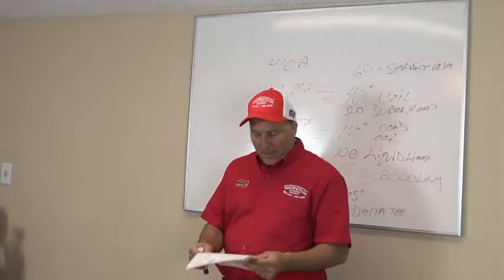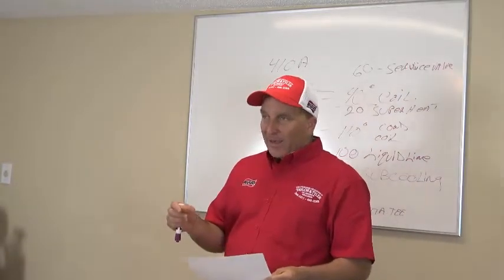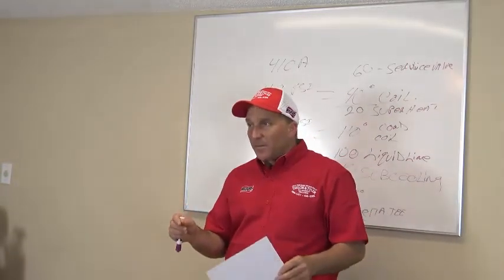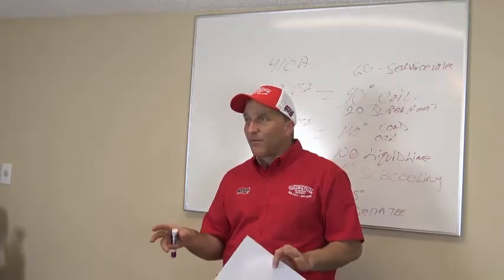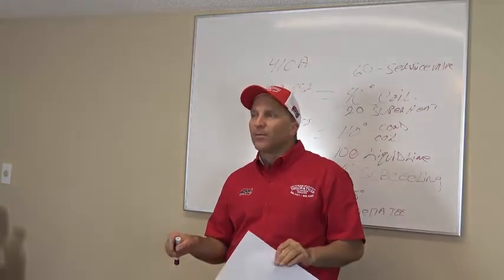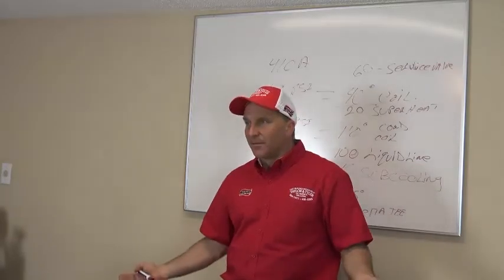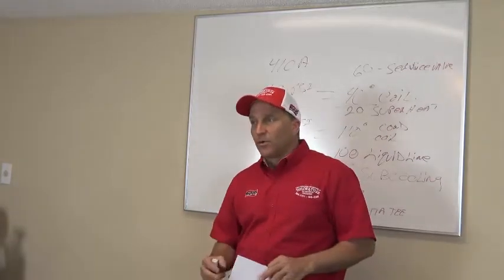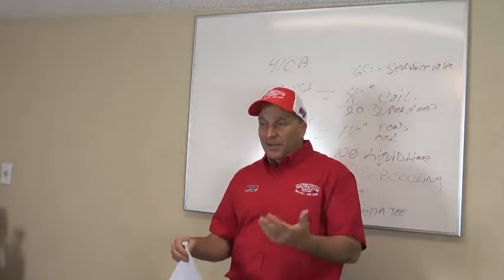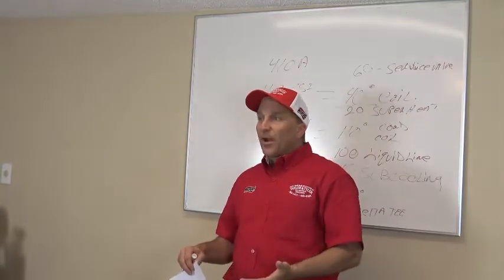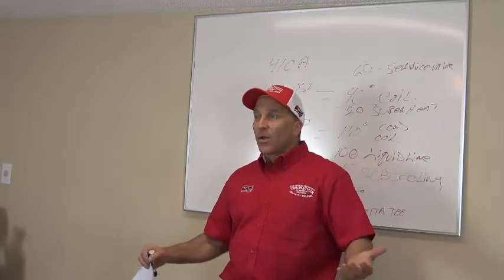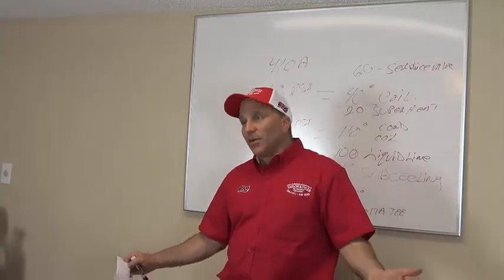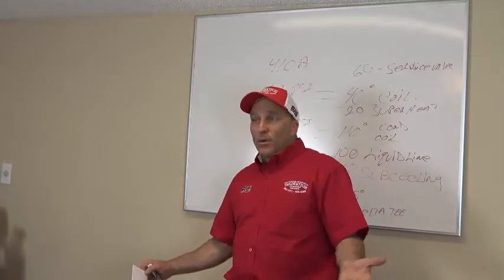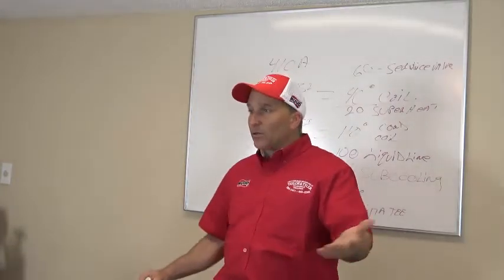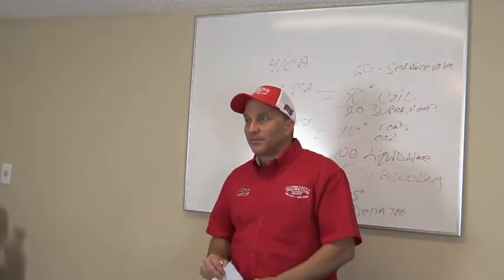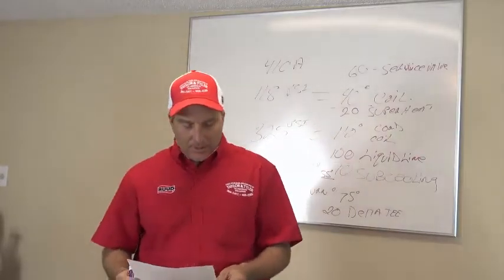Okay? So that, Ryan, is going to be my number one pet peeve on every service call you go to, and of course every PMA you have to clean. But every service call you go to, ma'am, I need to clean your condenser, because you can't get a proper head pressure unless the condenser's clean, right? Right. Okay, well, how can you go any further then, really and truly, when you think about it like that? Yeah. Do you know what your superheat and subcooling are? No, because you don't know what your head pressure is going to be once it's clean. Right. All right, guys, we're going to go ahead and do the next one here.